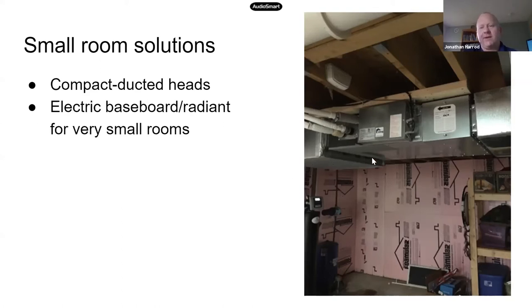And now, instead of having a 6,000 BTU head in each bedroom, we've got a 9,000 BTU air handler that splits its output between these three different rooms. So this is a really great solution. You have to have a place like a basement or a conditioned attic to put it. Another solution that we've used for very small rooms like bathrooms is to just put a small length of electric baseboard or a radiant towel rack or some other low output, low consumption heater in those rooms. They really don't need cooling. They can get that passively from the adjacent rooms.